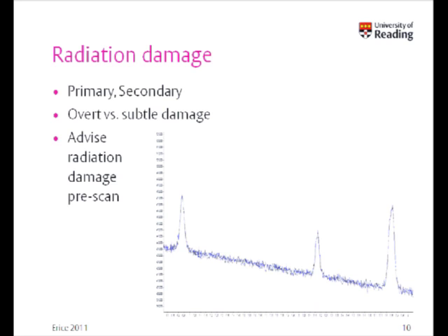And so to one of the many pre-experiments that's listed in Ian's chapter, I would now add that if you visit a synchrotron, then it is well worth adding a radiation damage pre-scan to your list of experiments. And here's a result of one done very recently at Diamond, a 2-minute data collection on a molecular organic in blue, followed by another 2-minute data collection. This was actually using the crystal analyzer detectors. We then quickly superimpose them one on top of another. There's no significant difference. So this sample is at least good enough to collect data for 4 minutes.